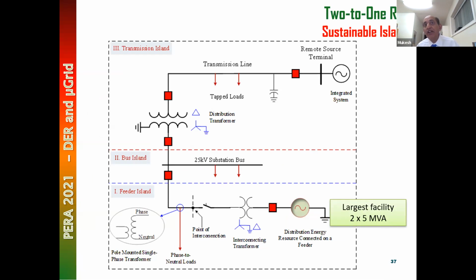Number 1, I wanted to make a point: this is a similar diagram as before. Transmission station, long transmission line, distribution load station, and the feeders. 3 feeders here, but I'm just talking about 1 feeder. One of the IPPs is 10 MVA, 2 generators of 5 MVA. The entire station load is less than 10 MVA. The point is this one IPP can supply the entire station load. So that means it can form a microgrid with a feeder, with all 3 feeders, even with some of the transmission loads.